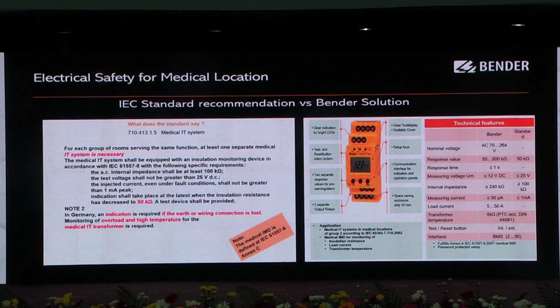You can see the 50 to 500 kilo ohms response value, and the response time is less than 1 second. You have to identify which feeder is faulty, which biomedical equipment is faulty. Again, in this current range you can see we are injecting 50 microampere; the standard says you have to inject less than 1 milliampere. So according to the standard, our product is qualified.